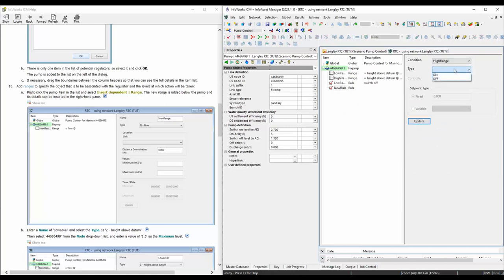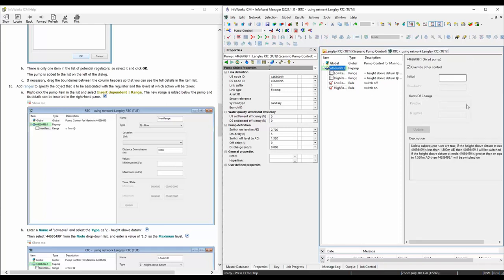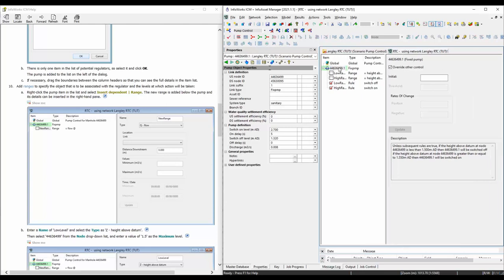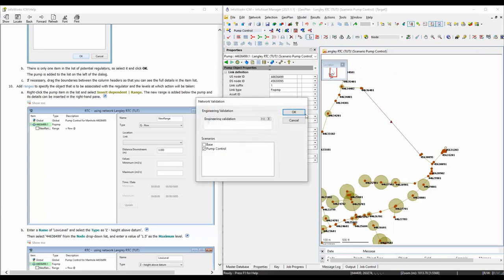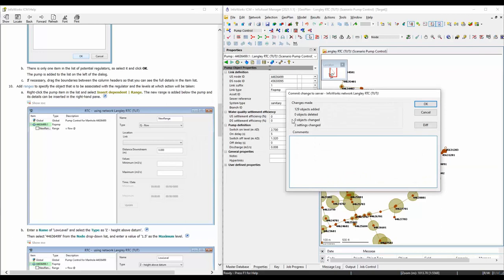Similarly, for the high range, add a new rule. Set condition to 'high range' and when it's on high range we want to turn it on - hit Update. So those are pretty much everything we need to enter. Make sure you click on the RTC rule and read this summary - it says: if the height above datum at this wet well node is less than 1.5, it needs to be switched off; if the height above datum is greater than or equal to 1.55, the pump needs to be switched on. This plain-English summary is much easier to understand. Let's validate the model and save it - calling this 'edit RTC for pump'.